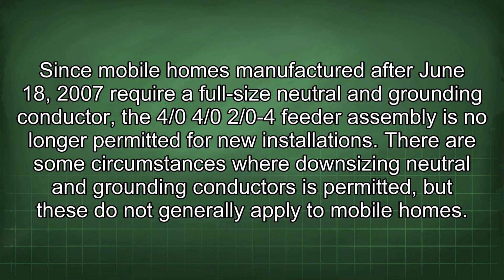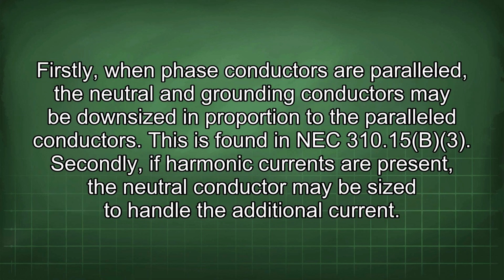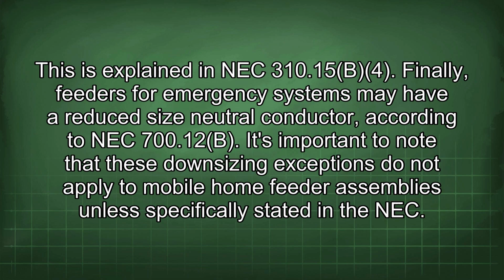There are some circumstances where downsizing neutral and grounding conductors is permitted, but these do not generally apply to mobile homes. Firstly, when phase conductors are parallel, the neutral and grounding conductors may be downsized in proportion to the parallel conductors. This is found in NEC 310.15b3. Secondly, if harmonic currents are present, the neutral conductor may be sized to handle the additional current. This is explained in NEC 310.15b4. Finally, feeders for emergency systems may have a reduced size neutral conductor according to NEC 700.12b.